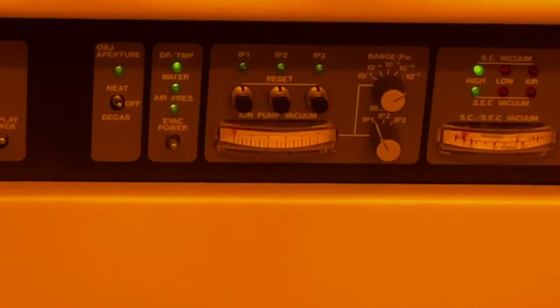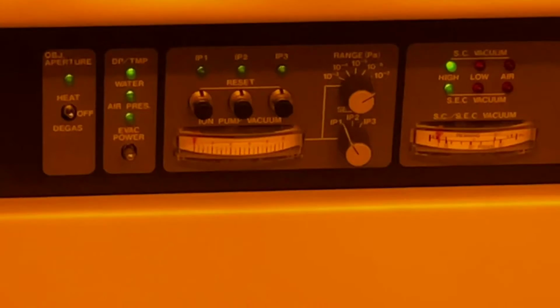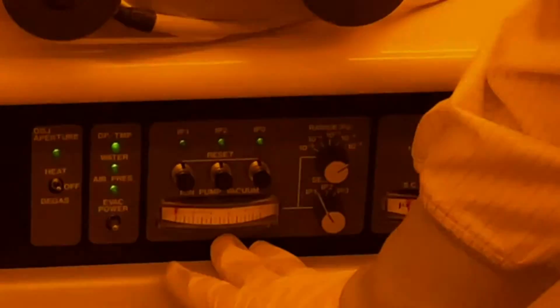Next, we have the objective heater. The aperture needs to be heated to prevent thermal stress. So this should be on as long as the vacuum is properly on. We also have the evac power, and then these three interlocks that determine whether or not this will be tripped. So when this is on, the vacuum system is turned on and connected to the system. When the air pressure, water, or DP/TMP are not satisfied, it will trip the system and it will turn off the evac power.